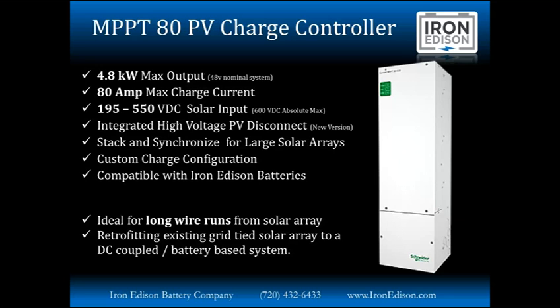The high voltage charge controller is ideal for a few different applications. One, if you have some very long wire runs between the solar array and your balance of system. I was actually curious, so I compared some industry standard wire pricing versus the price difference between the MPPT 60 and the MPPT 80 charge controller, and found that if you have a wire run of about 200 feet or longer between your solar array and the balance of system, by going with a high voltage configuration, which means you have smaller wire between the 2 points and the additional expense of the MPPT 80, you actually break even at 200 feet. So really, if you have less than a 200-foot wire run between the array and your charge controller, the MPPT 60 is probably the more economical choice, but if it's greater than that, I'd seriously consider looking at the MPPT 80 as well.